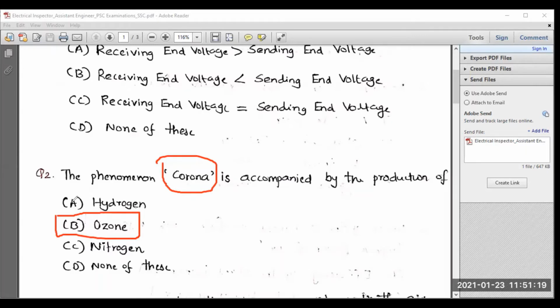The corona effect is mainly applicable for long and medium transmission lines, occurring mainly due to high voltage. It is basically an electrical discharge. Air is a dielectric medium, not perfectly insulated, and it supports the movement of electrons. If the voltage between the two conductors exceeds the threshold voltage, or critical disruptive voltage, the corona phenomenon will take place.